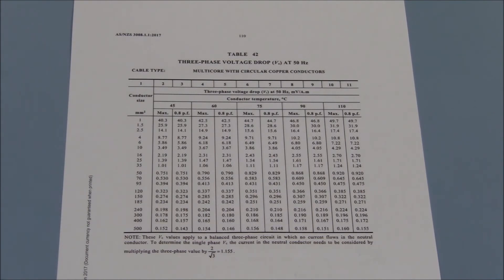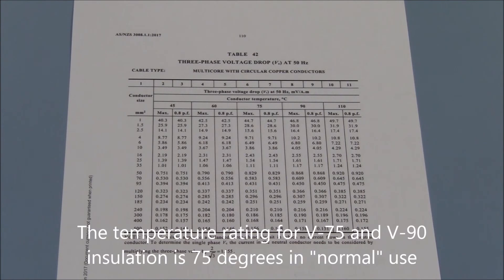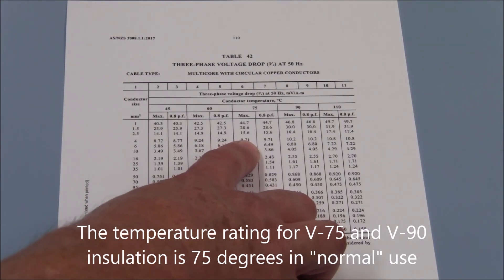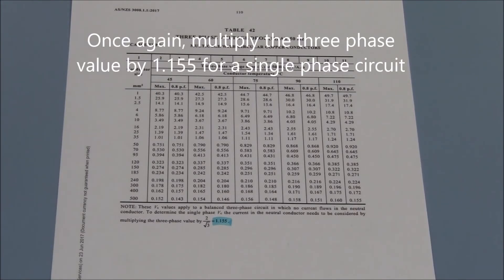Consulting table 42 column 6 for 75 degrees, the value of VC is 9.71. However, as this is a single phase circuit we need to convert this three phase value by multiplying it by 1.155 as per the footnote at the bottom of every voltage drop table.